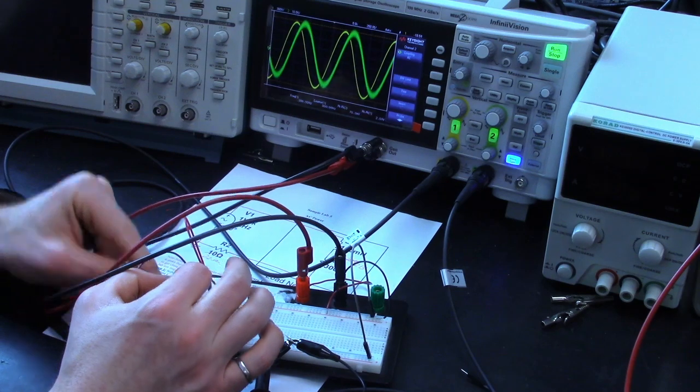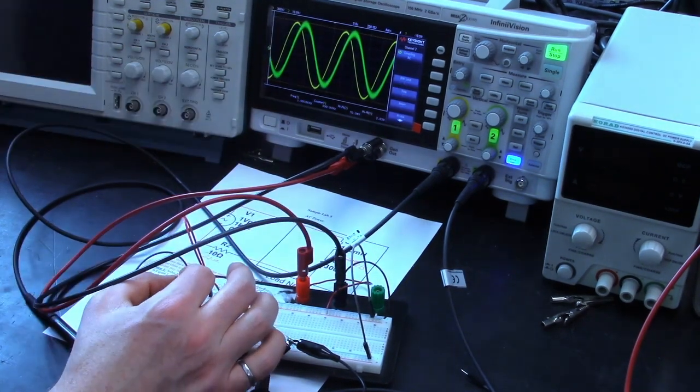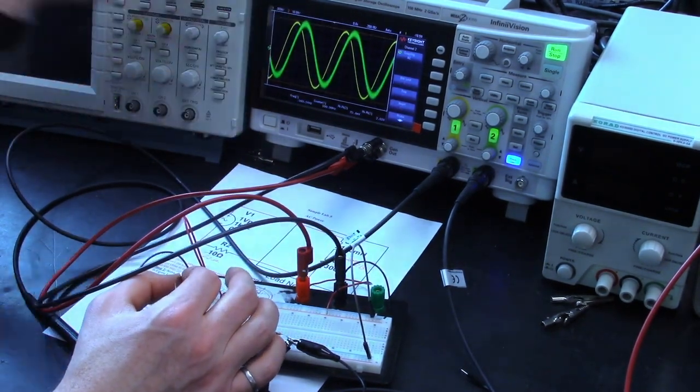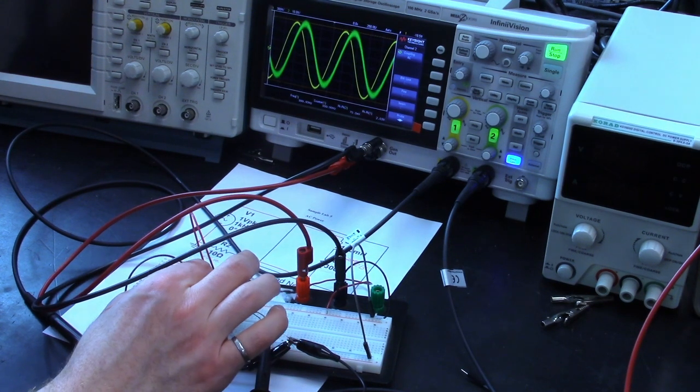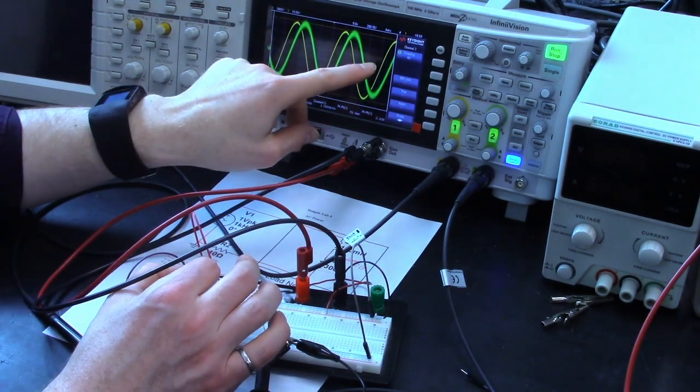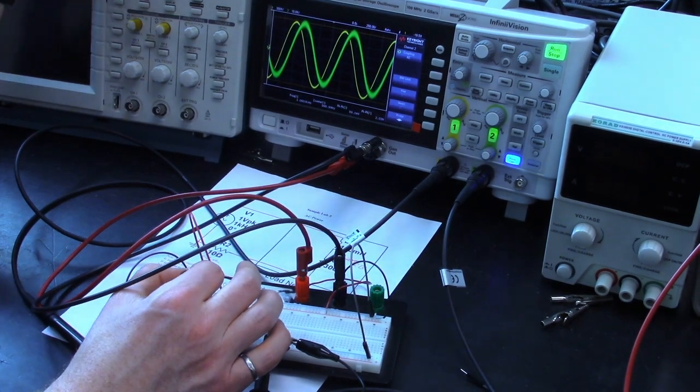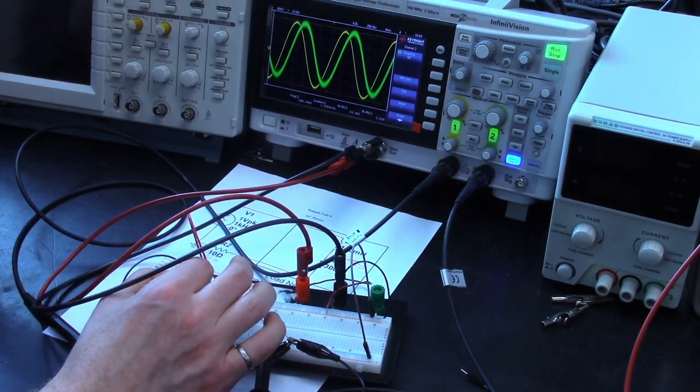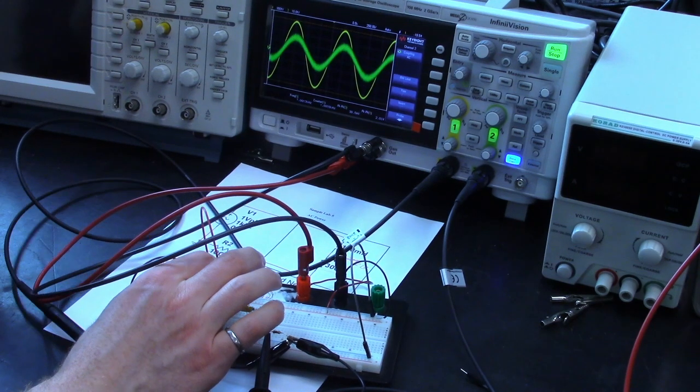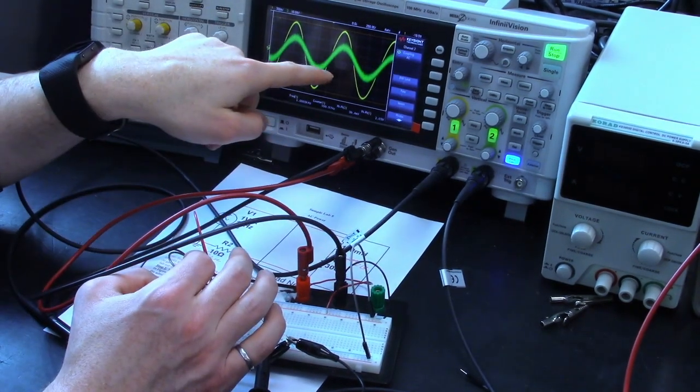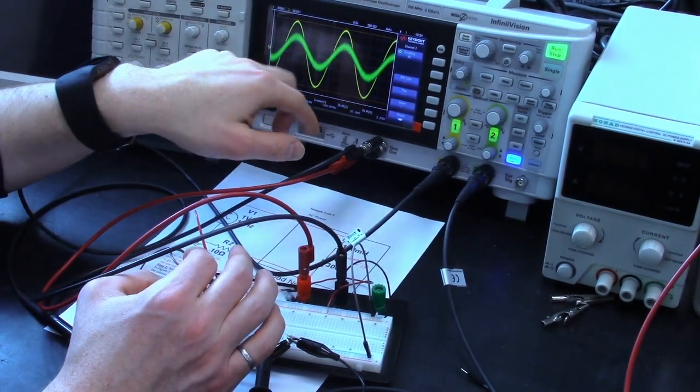So now if we look at the scope we see that we have our current that's phase shifted and higher amplitude. And if we hook up these capacitors what we should see is that the current phase shifts to line up with the voltage and reduces an amplitude. And there we go, so we've shifted over to the left. Now they're more or less in phase and the amplitude has reduced.